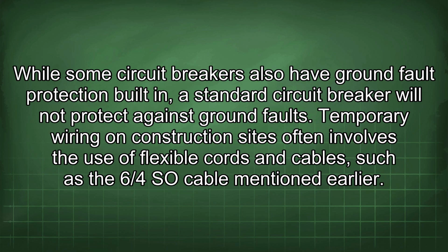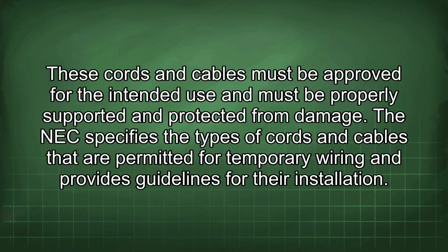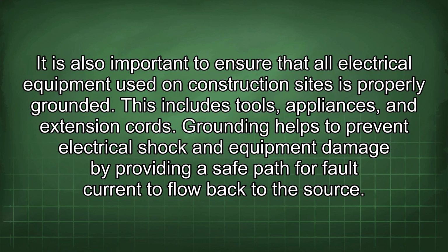Temporary wiring on construction sites often involves the use of flexible cords and cables, such as the 6/4 SO cable mentioned earlier. These cords and cables must be approved for the intended use and must be properly supported and protected from damage. The NEC specifies the types of cords and cables that are permitted for temporary wiring and provides guidelines for their installation. It is also important to ensure that all electrical equipment used on construction sites is properly grounded.